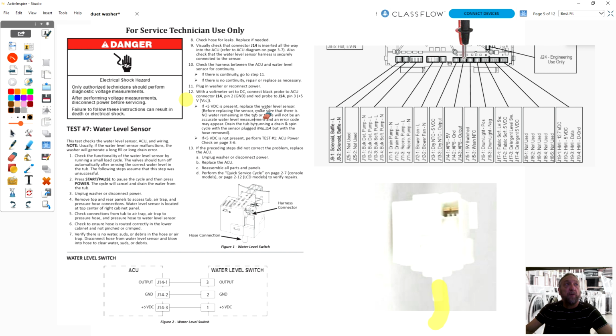So they're telling you, if you get 5 volts DC, replace the sensor if you're having these problems. That's it. Because the board only takes information that comes off this output. The voltage coming in on the DC and ground is just sending power to the sensor, so the sensor can read and measure the water level by the air pressure that's going inside of it. So these two are just supplying power to the sensor, and then that sensor sends a feedback signal to the control board.